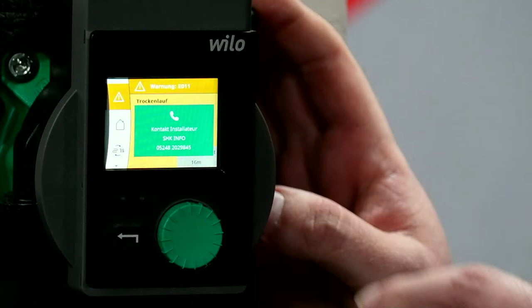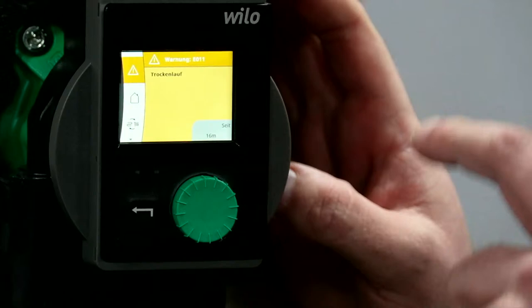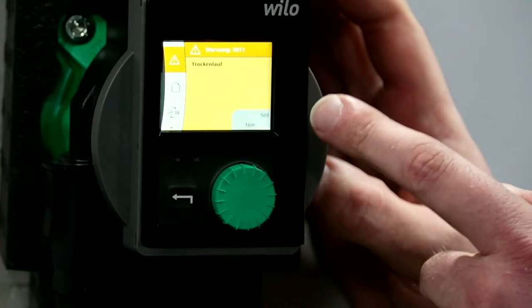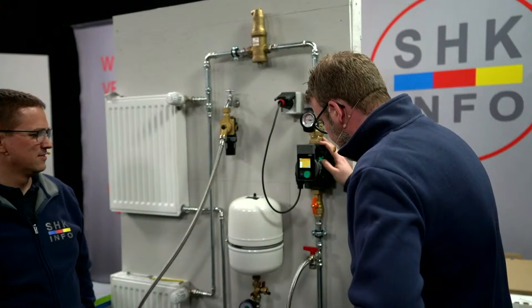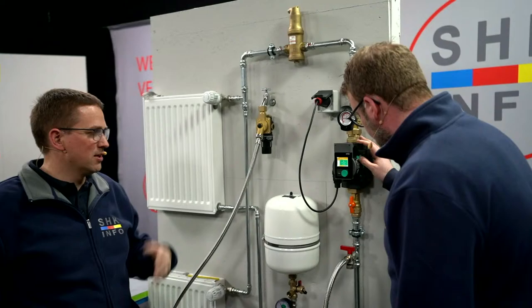Das ist natürlich ein Riesenvorteil von diesem neuen großen Display – ich habe hier keine Fehlermeldungen mehr mit irgendwelchen Hieroglyphen, sondern eine Volltextanzeige. Es ist kein Druck mehr auf der Anlage – das haben wir gerade ein bisschen provoziert. Und zwischendurch blendet er direkt ein, wo man jetzt anrufen soll beim Installateur. In diesem Fall SHK-Info. Super praktisch. Das Schöne ist ja auch an der Pumpe, dass die automatisch erkennt, wenn der Trockenlaufschutz nicht mehr besteht, weil wir wieder Anlagenwasser aufgefüllt haben. Die Pumpe sollte dann automatisch in Funktion gehen.